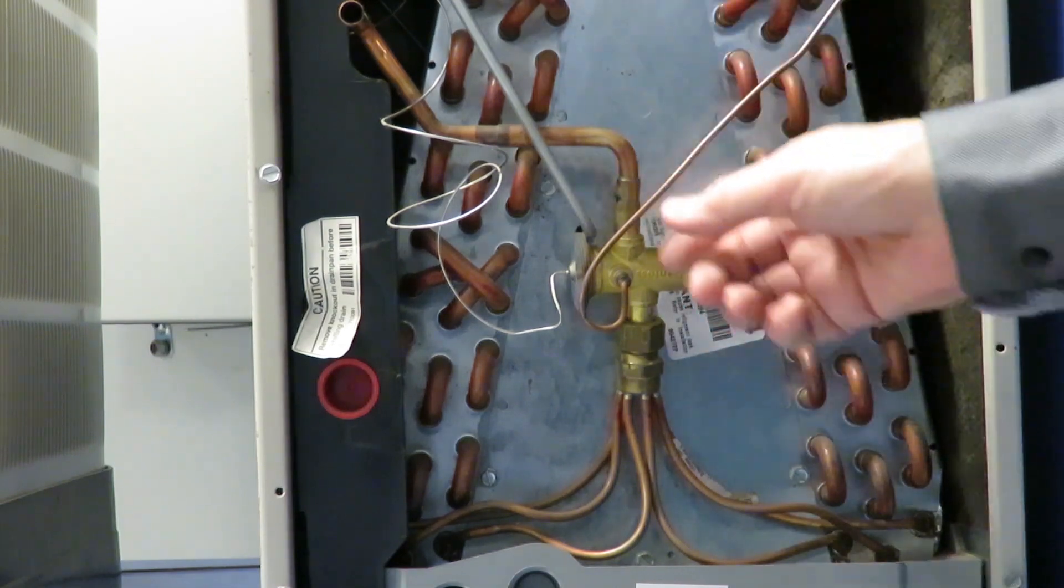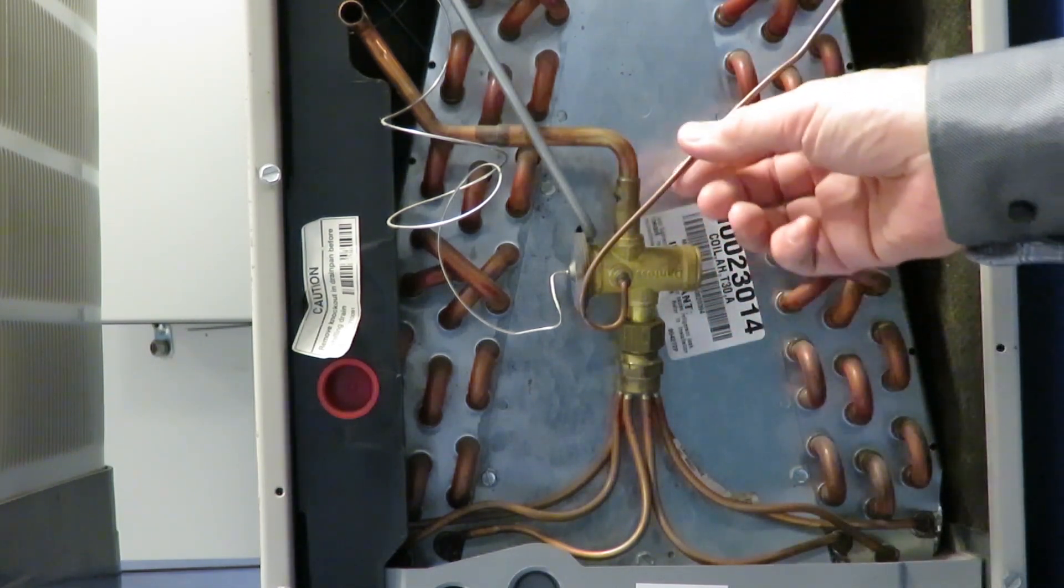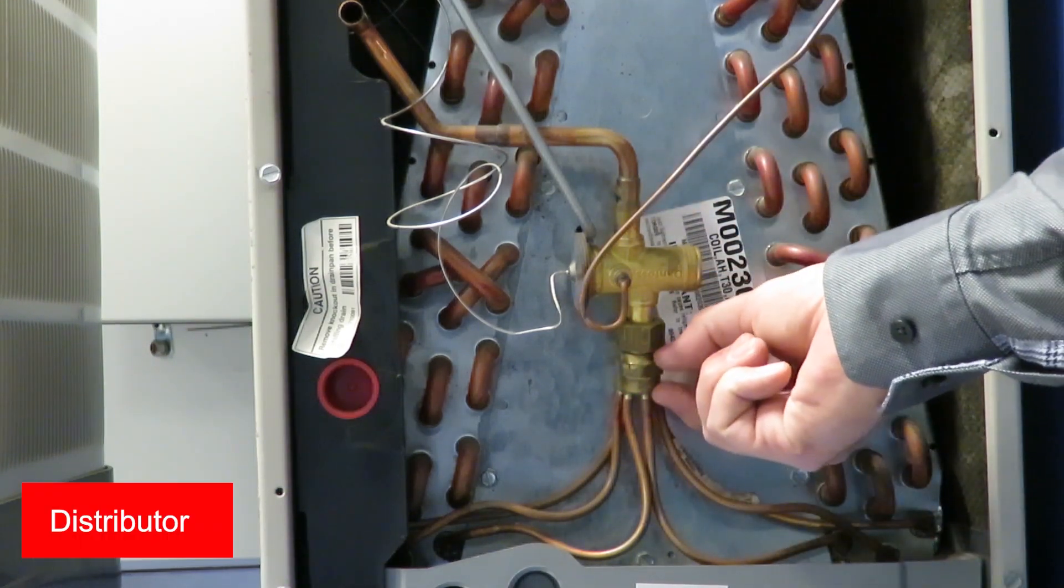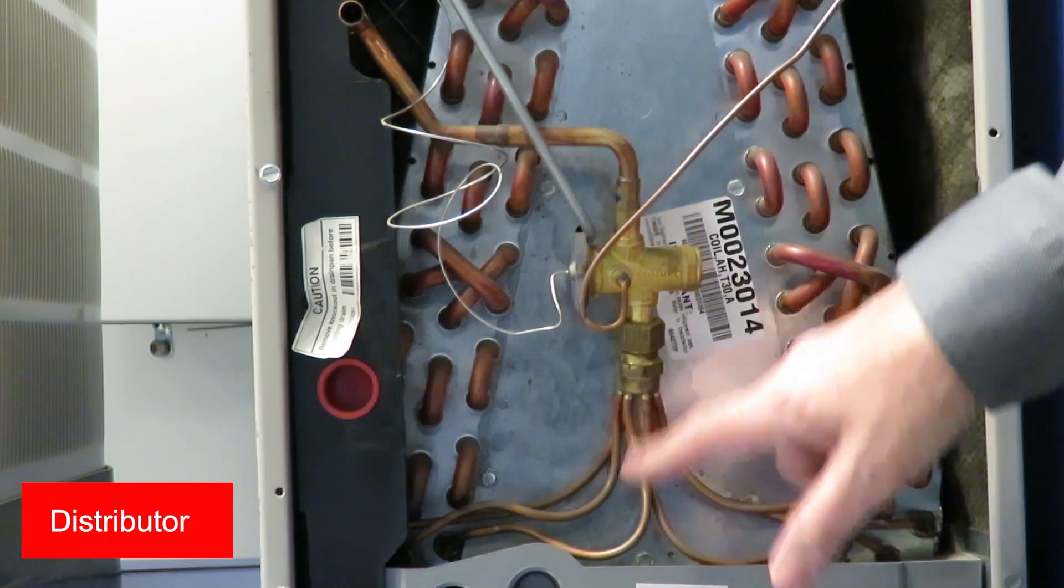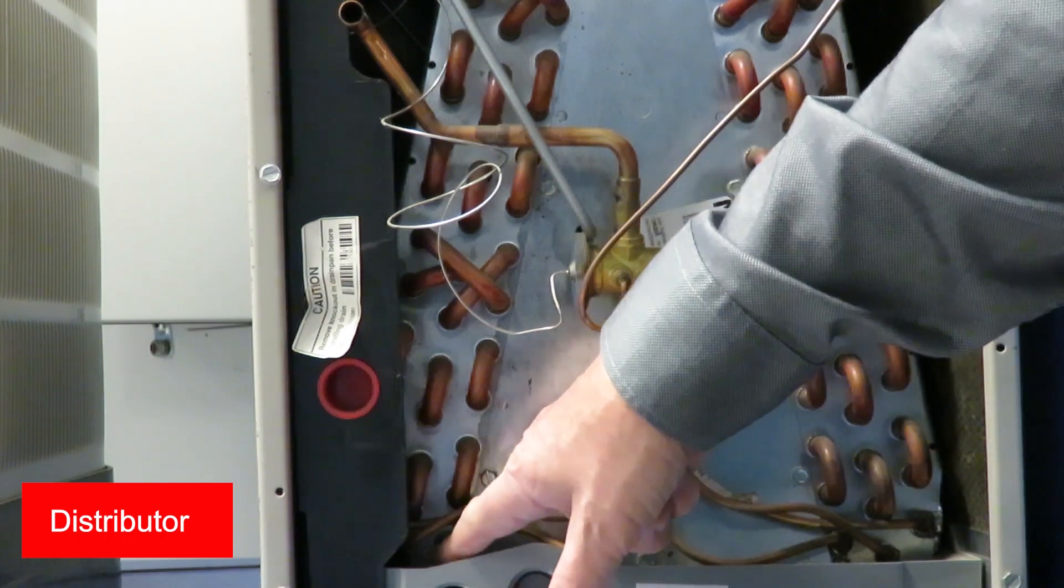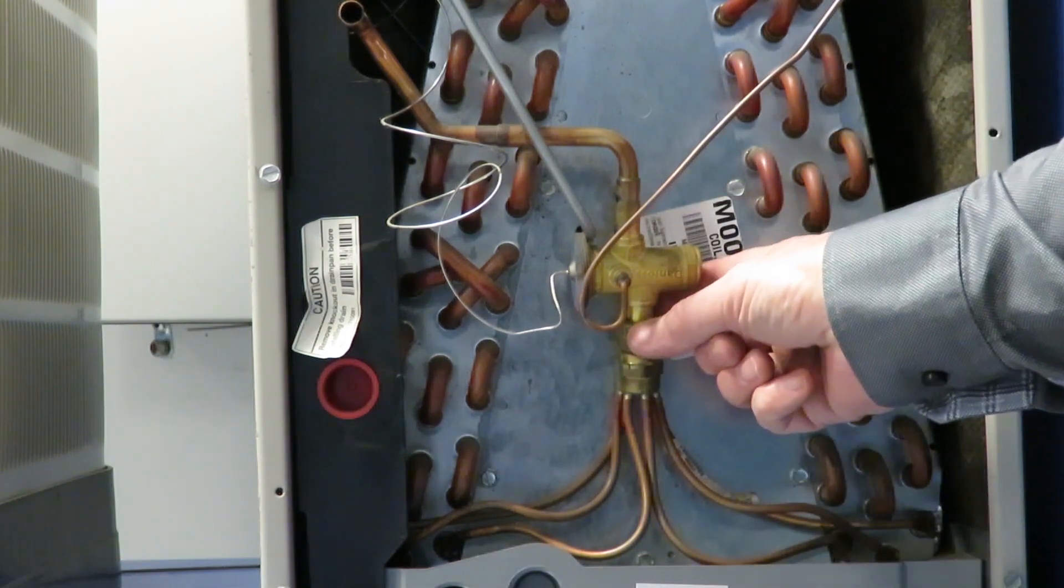We will show you later on in another close-up where that is put. Then we have the outlet. This is a separate component, a distributor you buy. You braze in your smaller copper tubes that will connect to the evaporator inlet, and then this is screwed on the valve.